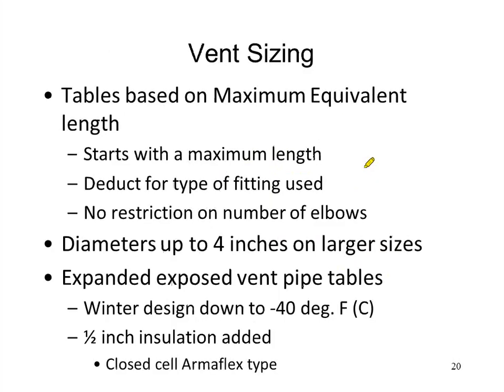All right, on the venting side, the venting is actually very beneficial in terms of what's allowed with this unit, and I'll show you the tables here in a second. We do it based on maximum equivalent length. That means we're going to give you a total equivalent maximum, a certain number of feet, and within that number of feet, it counts all the actual length of pipe as well as any penalties for elbows and joints and things like that.